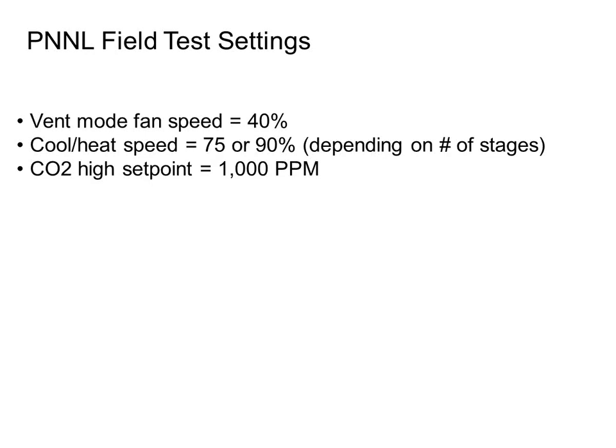You'll notice that they never ran at 100% at all, because in nearly 100% of the buildings across the entire country, all fans are oversized. Just like all cooling systems are oversized, and all boilers and all furnaces and everything else that all of us have ever done in our entire careers, we're all oversized. So they didn't even bother going to 100% airflow. They just went to 90, right? And that was sufficient for what they were trying to do.